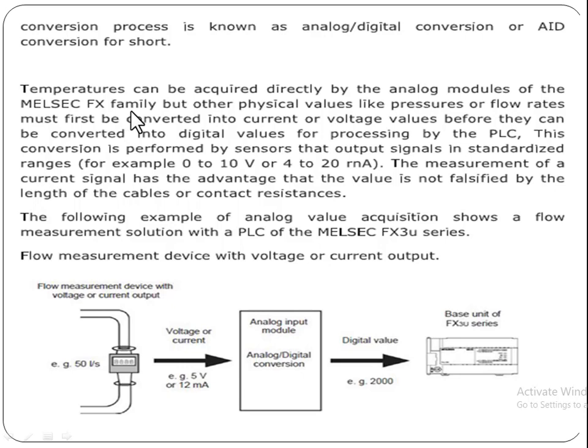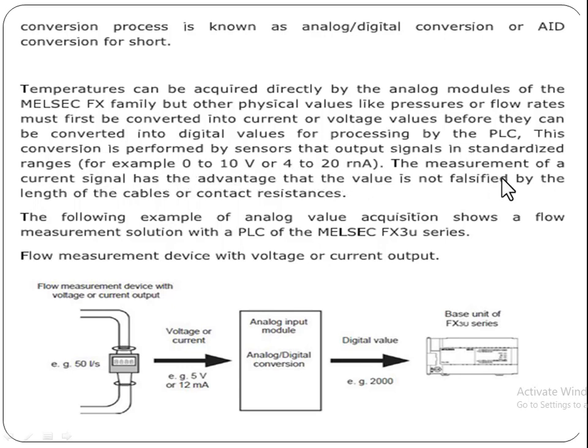Other physical values like pressures or flow rates must first be converted into current or voltage values before they can be converted into digital values for processing by the PLC. This conversion is performed by sensors that output signals in standardized ranges, that is 0 to 10 volts or 4 to 20 milliamperes.